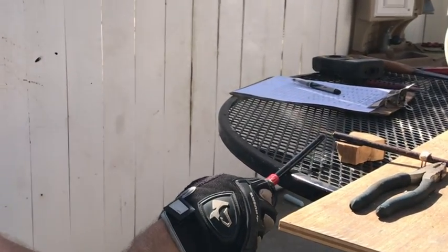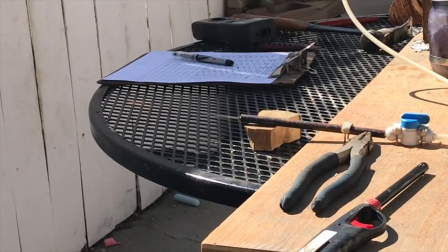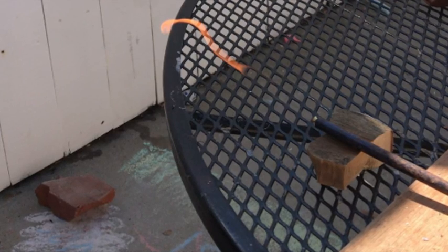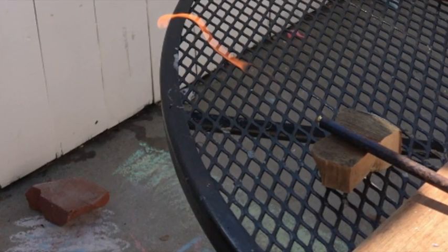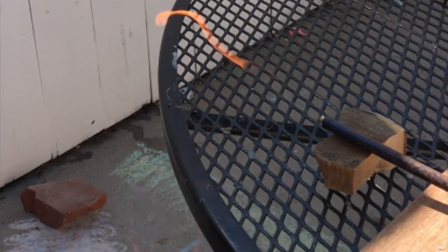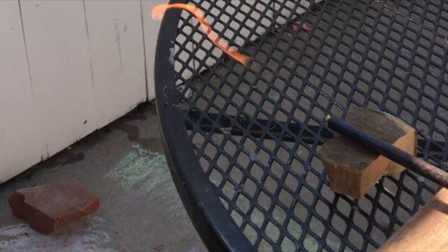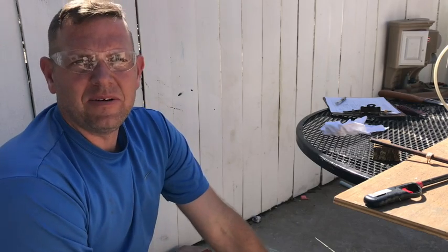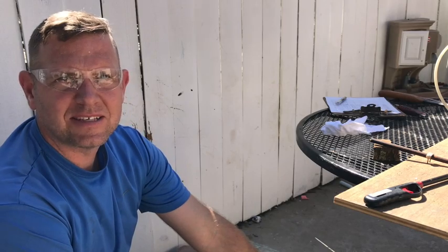Moisture dripping from the vent was noticed several times. It did seem to affect the flammability of the gas. When little or no moisture was present, the gas was more easily ignited. When visible moisture was at the vent, the gas was more difficult to ignite. While the gases never burned for more than 2 or 3 seconds at a time, the system was able to generate flammable gas.